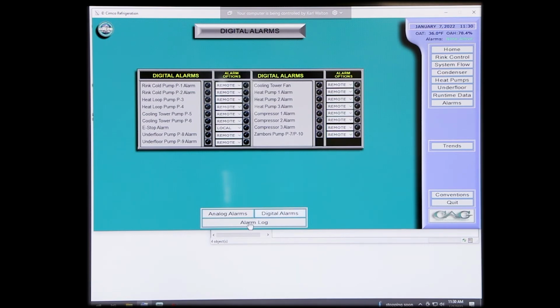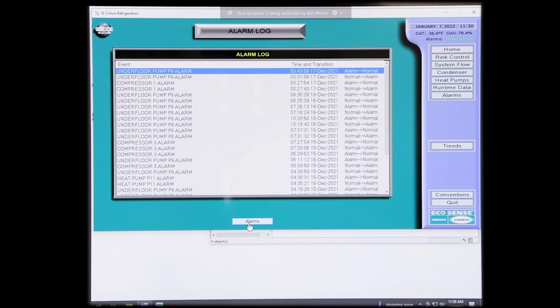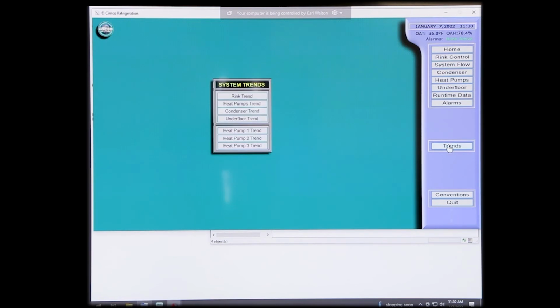And then you have the alarm log, which is just telling you exactly what failed and when. And when did it return to normal? Did it return to normal? Did somebody reset it? It's all here. We know what goes on. Okay, trend logs. This is a fun one. This is where you get to see how you're doing.